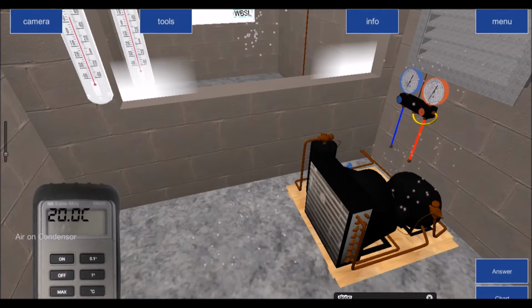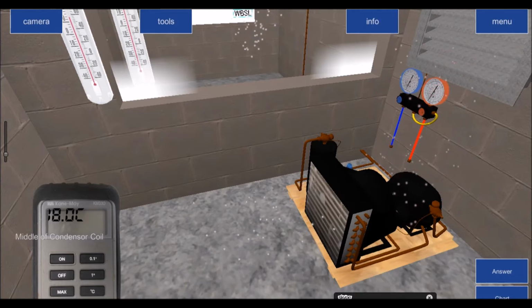So depending on whether you're on heating mode or cooling mode determines which heat exchanger is acting as which. But in refrigeration terms, you always have an evaporator which absorbs heat. You always have a condenser which rejects heat. And in this case, our condenser here has an air on temperature of 20 degrees and a condensing temperature of 18 degrees. So in our chart, is LP too low? Yes. And straight away then, without putting gauges on, I never put a gauge on the system, I can tell you with confidence the problem with this particular system is a lack of compressor capacity.